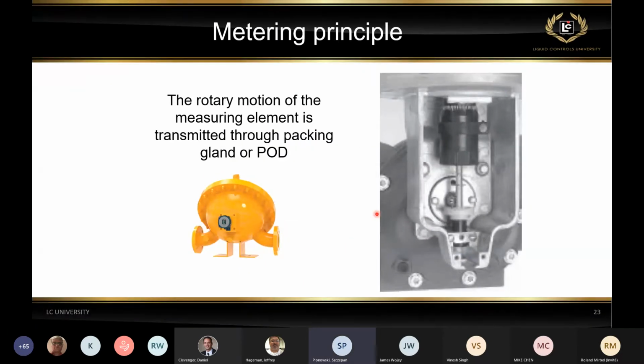Now, as the meter turns, and again, this is still kind of a little reminder from the previous training, the rotation of internal components of the meter is transferred to the outside of the meter through either a packing gland that's going to drive gears, or to a pulse output device. So we're taking rotation of the internal components and giving a pulse signal directly to some other electronic registration.